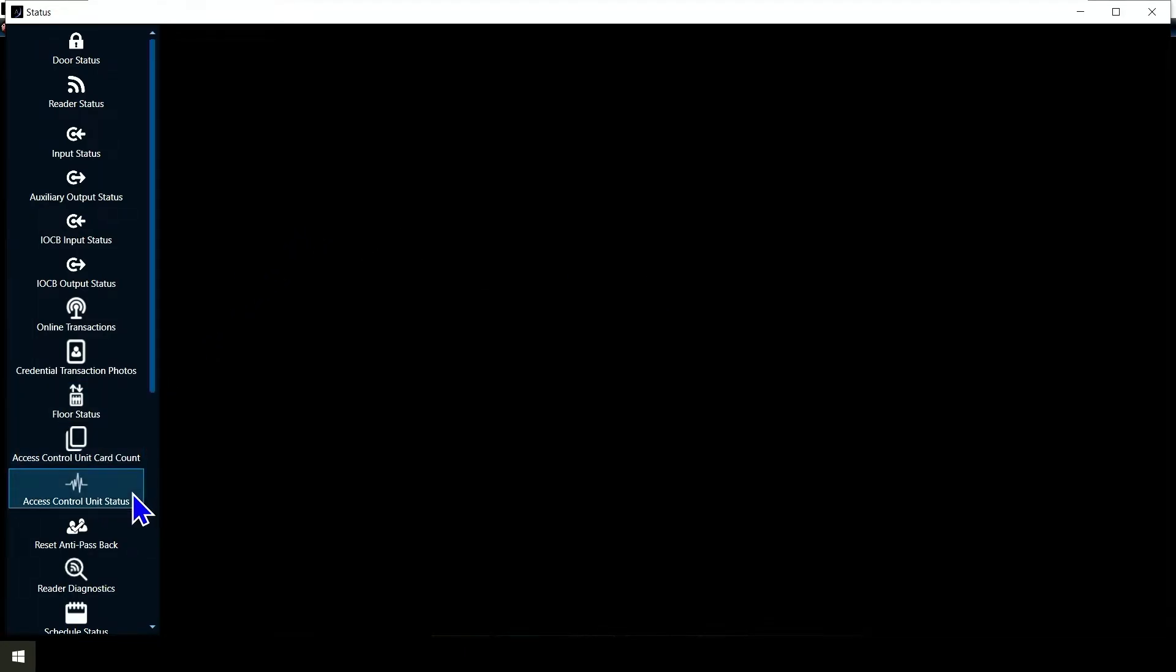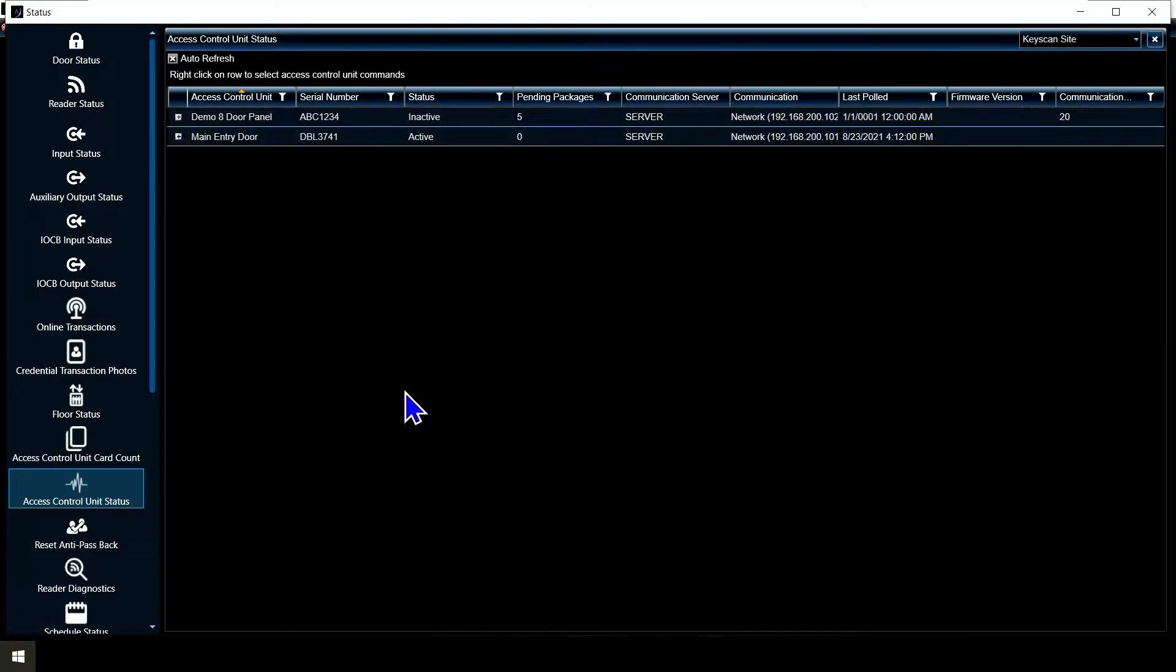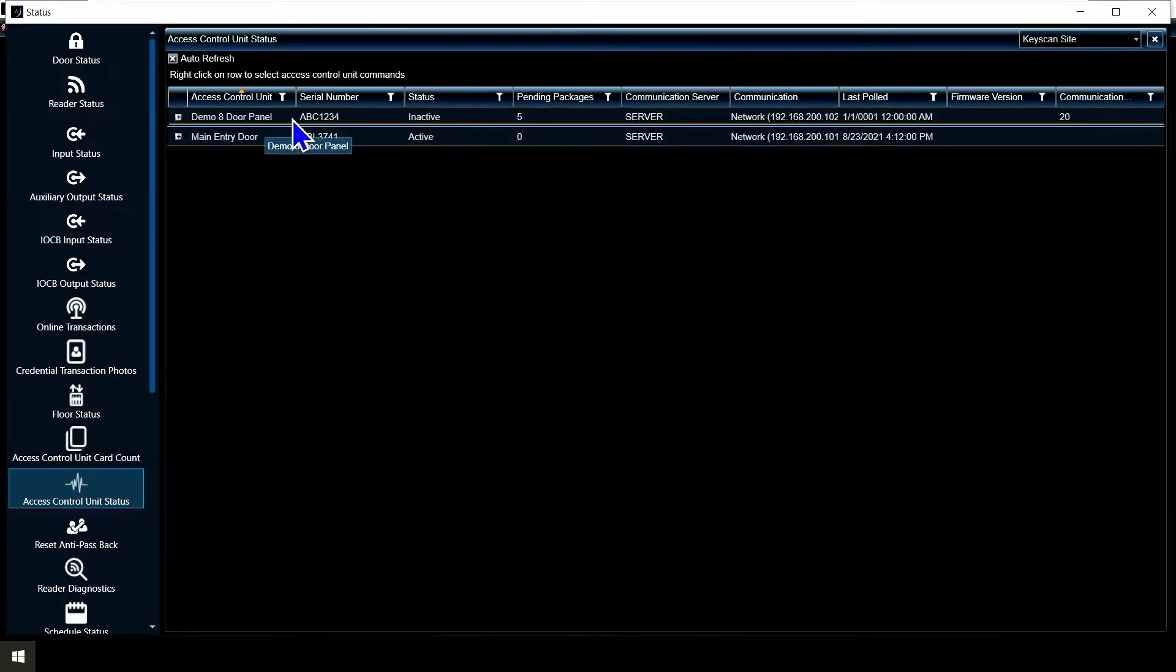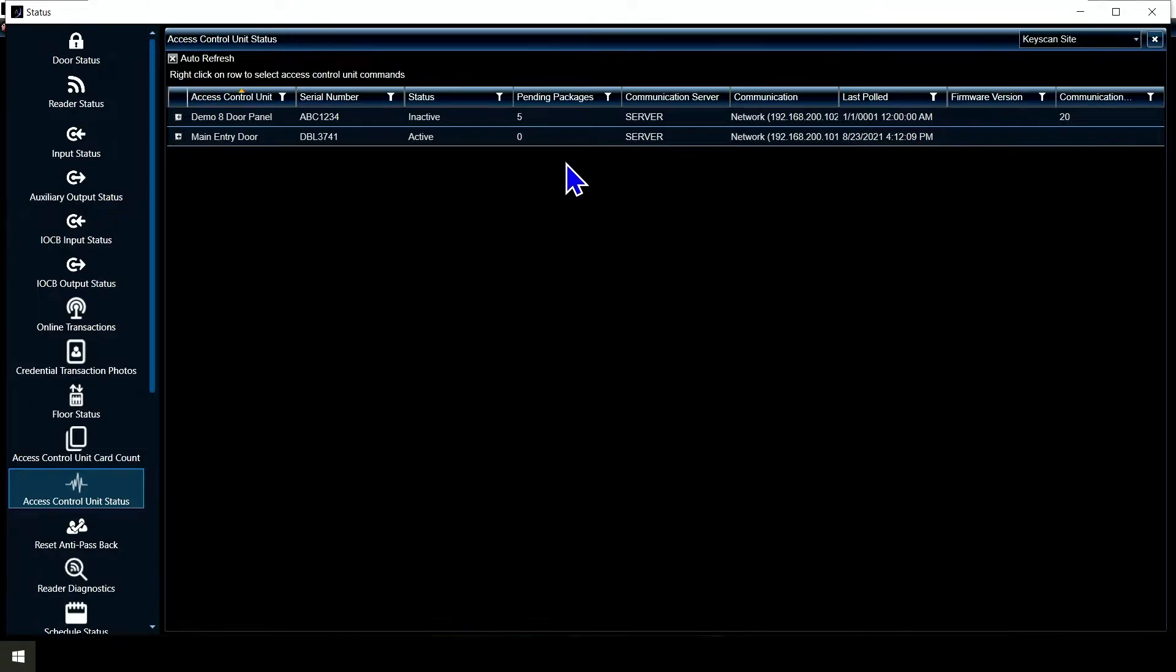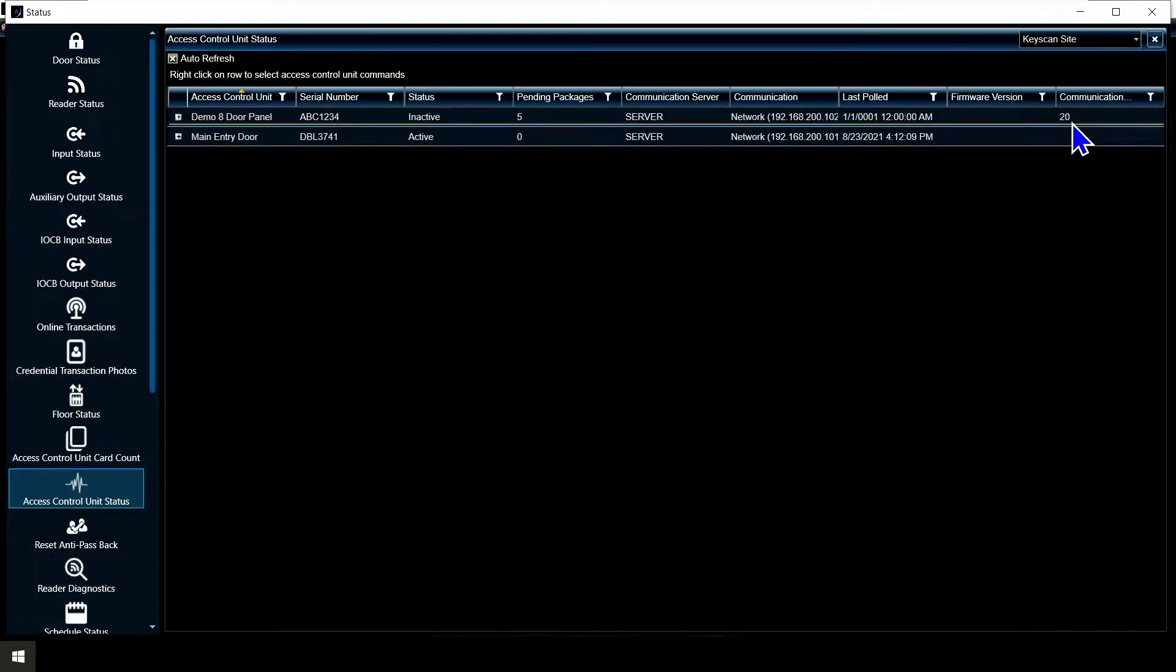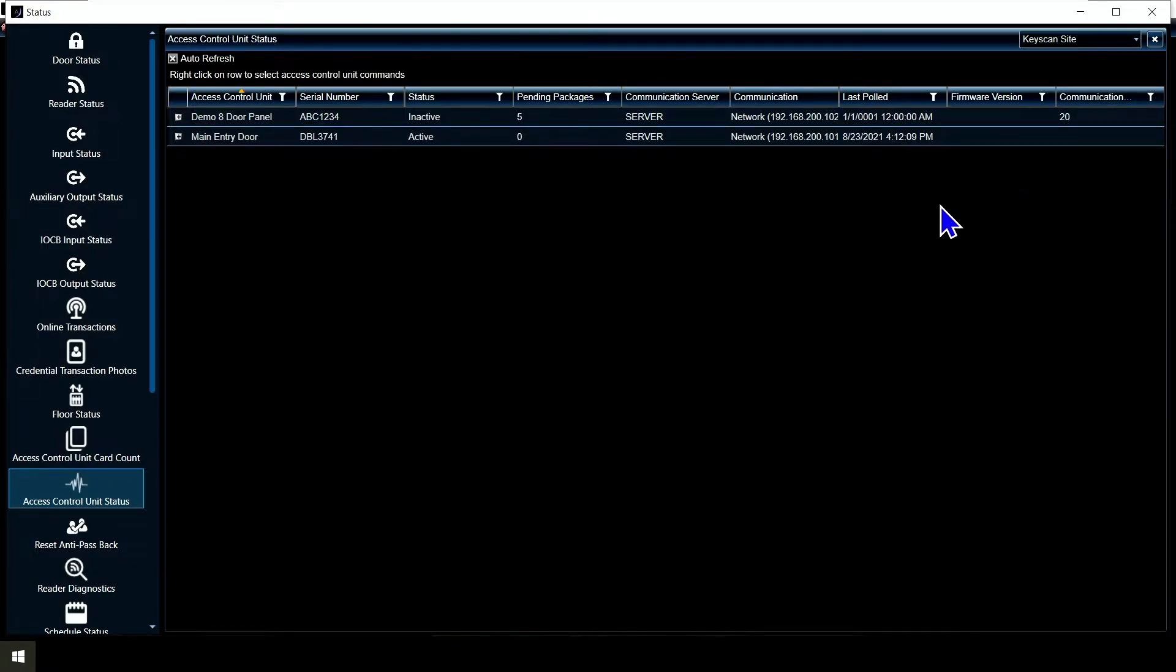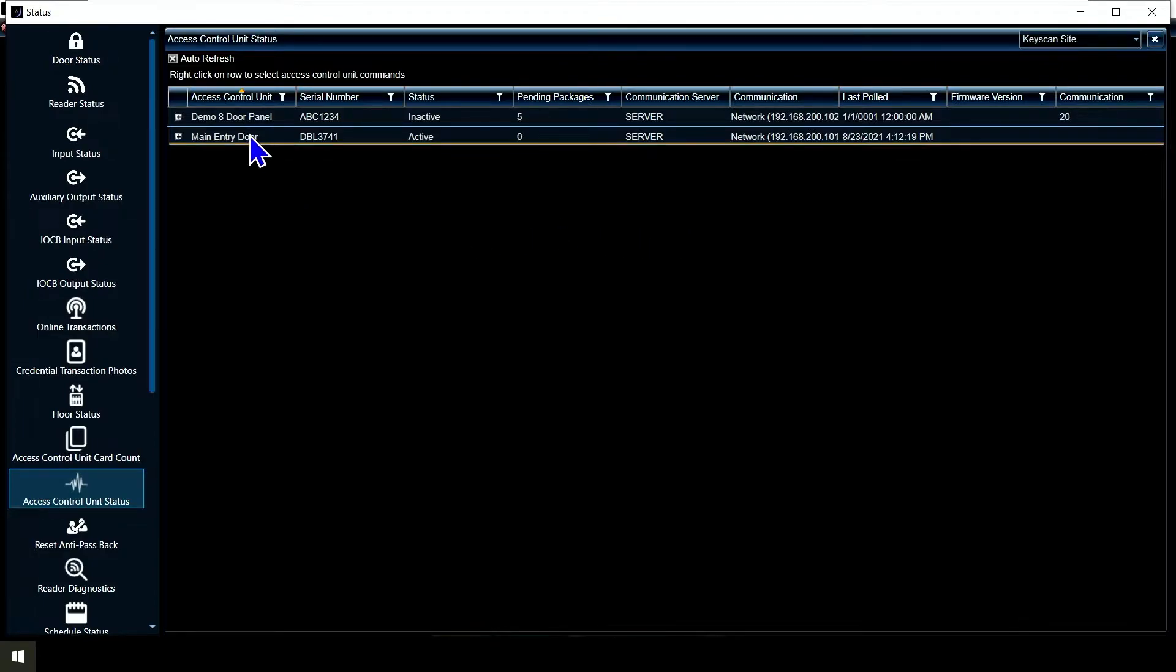I'm going to double click on it and it brings it up. Now we see my demo 8-door panel is showing inactive because I don't actually have an 8-door panel. That's okay because you can see what happens when something's not communicating. It's got a communication error over here of 20, basically telling me I can't find that panel. But my main entry door here is the panel I actually do have.